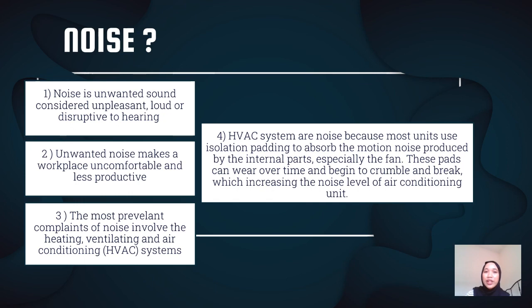Noise. Does everyone know what noise is? Okay, noise is unwanted sound considered unpleasant, loud or disturbing to hearing. Unwanted noise makes a workplace uncomfortable and less productive. Then, the most prevalent complaints of noise involve the heating, ventilating and air conditioning, which is the HVAC system. HVAC systems are noisy because most units use insulation padding to absorb the motion noise produced by the internal parts, especially the fan. This part can wear over time and begin to crumble and break, which increases the noise level of the air conditioning unit.